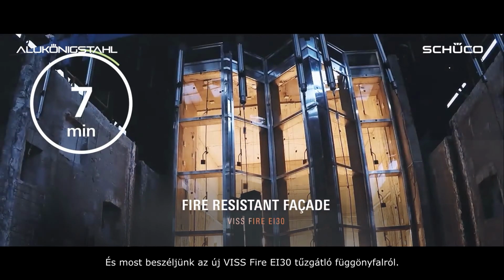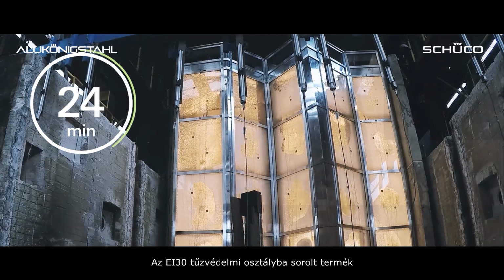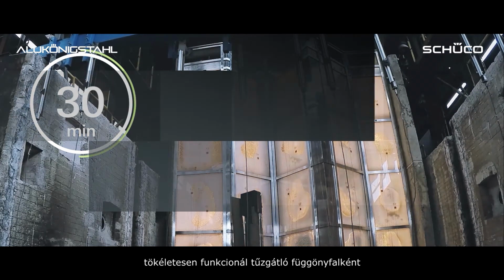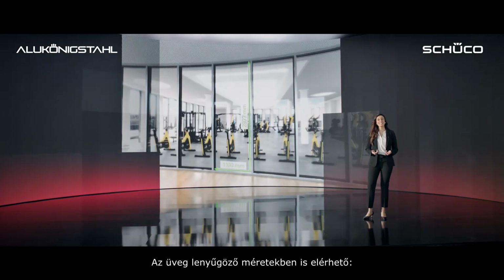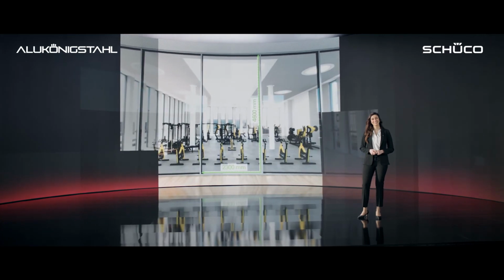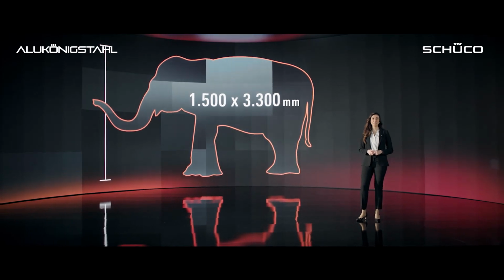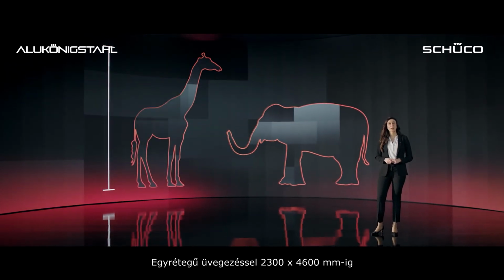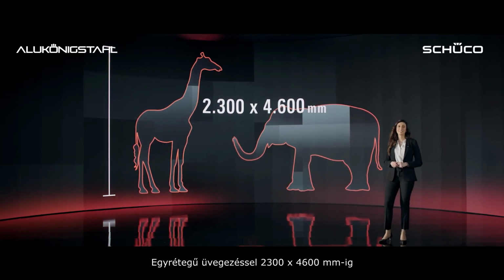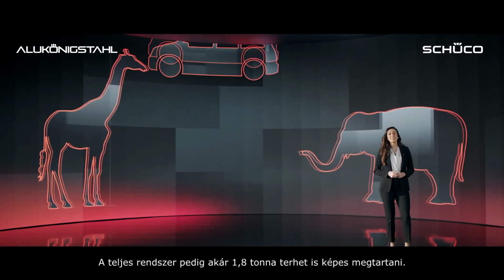And now on to our new VISS Fire EI30 fire-resistant facade. With its fire resistance class of EI30, it is ideally suited as a fire-resistant curtain wall or as a partition wall indoors and outdoors. The glass is also available in impressive sizes, with insulating glass up to 1500 by 3300 millimeters, as large as you can see here, with single glazing up to 2300 by 4600 millimeters, for example in building interiors. And the whole system can support weights up to 1.8 tons.